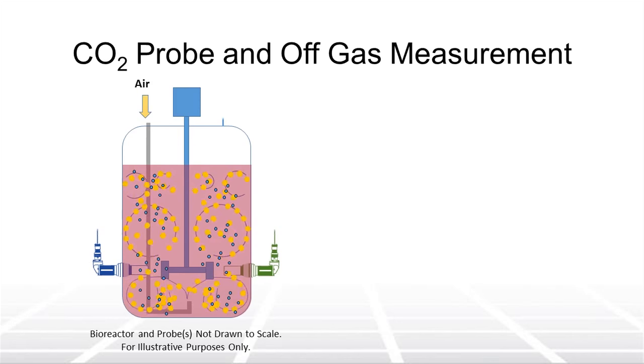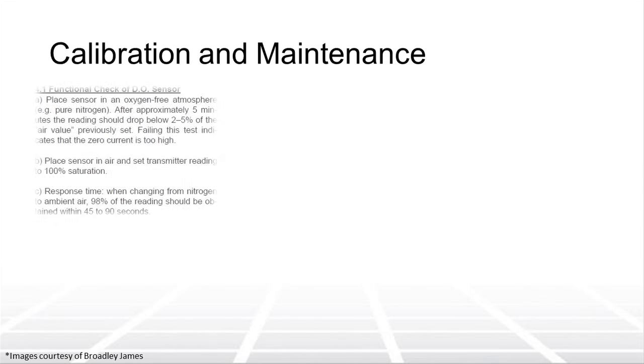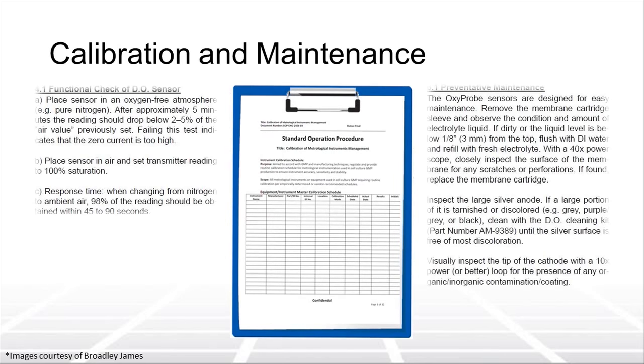On a commercial production scale, CO2 is often measured using off-gas analysis. Routine calibration and regular cleaning and maintenance are necessary in order to preserve the functional integrity of these instruments. A recommended maintenance schedule can usually be ascertained from the probe's manufacturer.